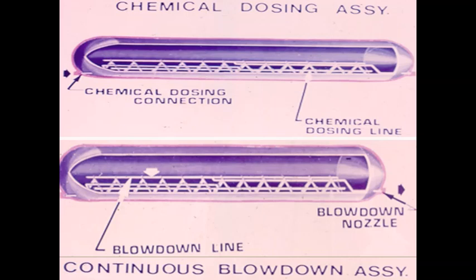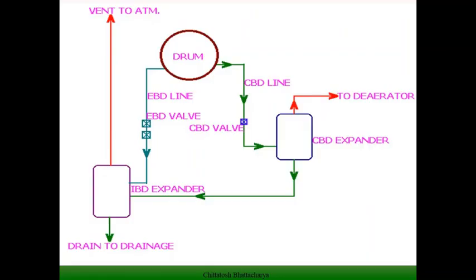saturated condition, because at lower pressure silica gets separated from the steam and it may attach to turbine blades, thereby creating problems of vibration. So we continuously monitor the silica concentration in the boiler drum water, and it should be within the 4 ppm level or below that.